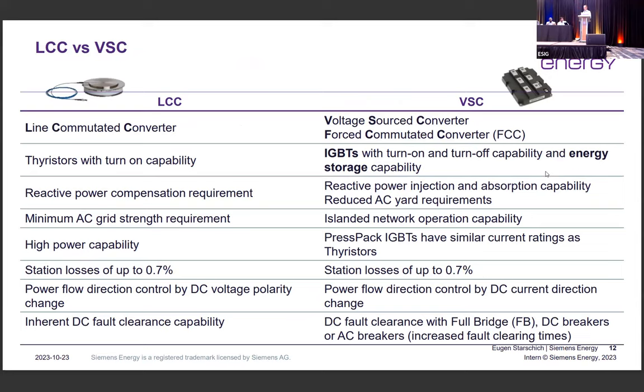This is, from my point of view, a kind of chicken and egg problem. We have DC breakers, they are different technology, and the main question is, how long should it take to clear a DC fault? And we are talking really about milliseconds. If we look at how fast an IGBT based converter, like a full bridge, can clear the DC fault, a full bridge can clear the DC fault within a few microseconds. Looking at mechanical DC breakers, we're looking at milliseconds. And depending on the DC network topology, you might want to have clearance in microseconds, or you can do it in milliseconds.